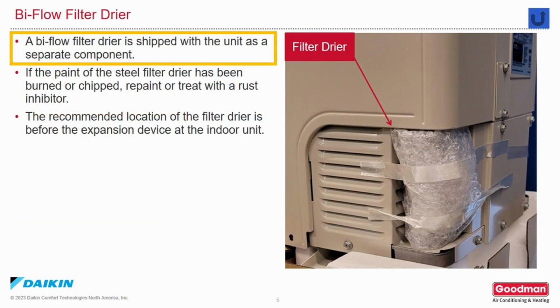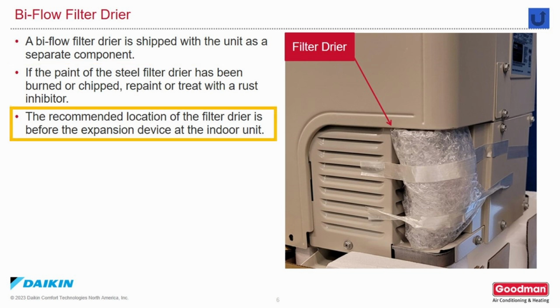Since this is a conventional heat pump, it is shipped with a bi-flow liquid line dryer. If during the installation of that dryer it would become chipped or burned, repaint the dryer or coat with a rust inhibitor to ensure the integrity of the refrigeration system. The recommended installation location for the filter dryer is before the expansion device in the indoor unit.